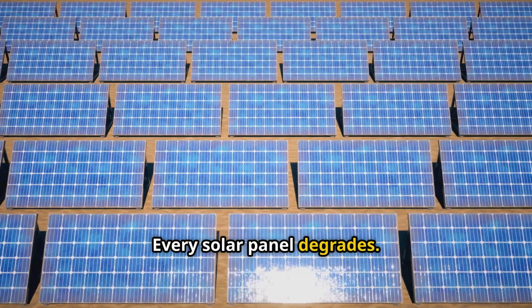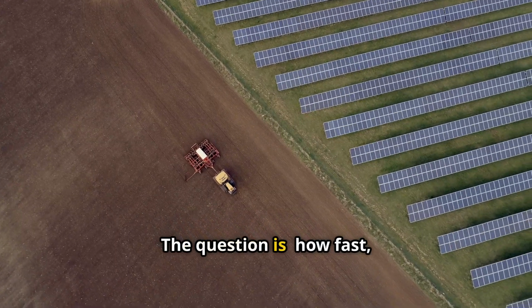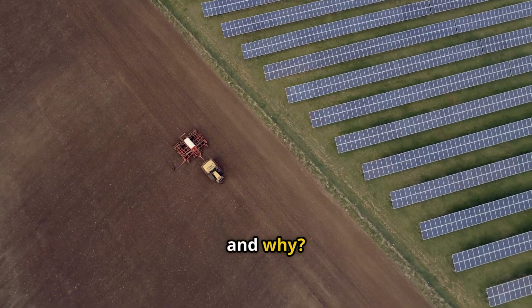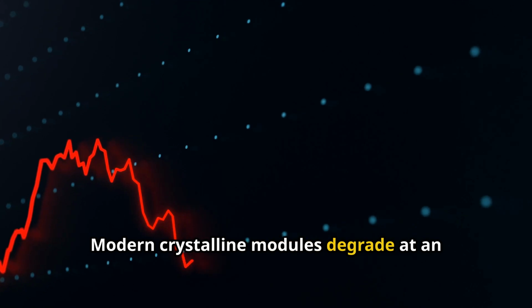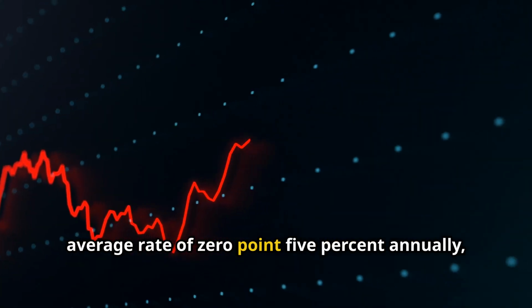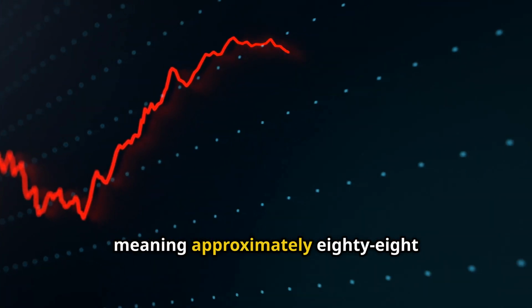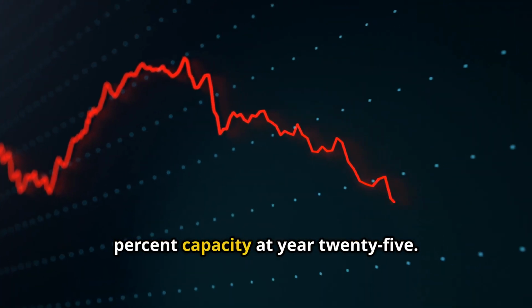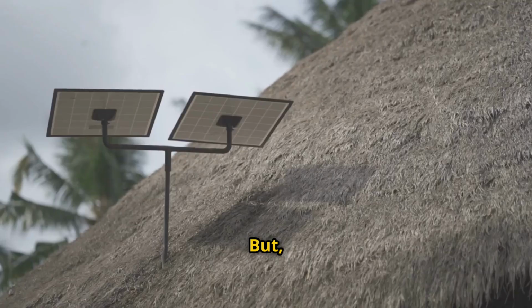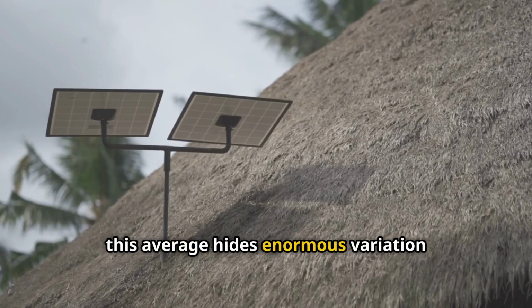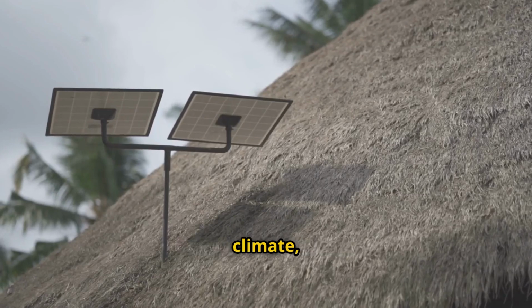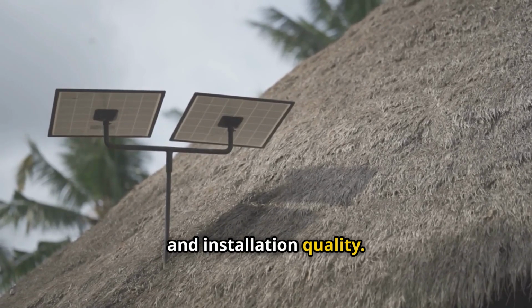Every solar panel degrades. The question is, how fast and why? Modern crystalline modules degrade at an average rate of 0.5% annually, meaning approximately 88% capacity at year 25. But you know, this average hides enormous variation based on technology, climate, and installation quality.